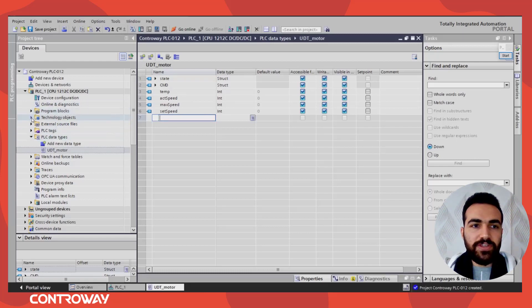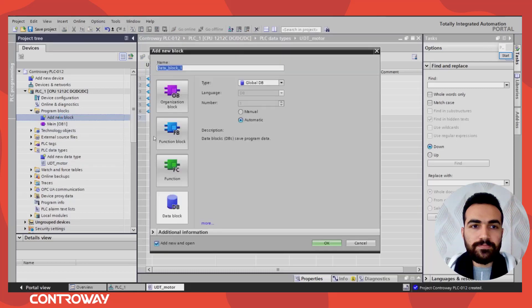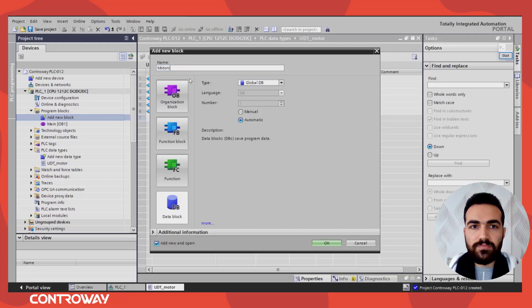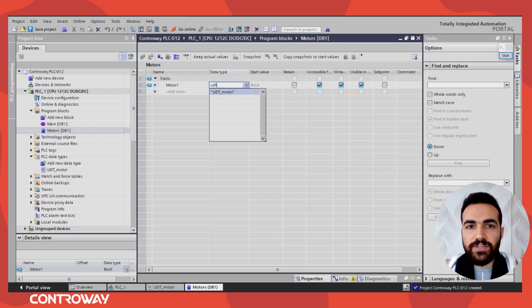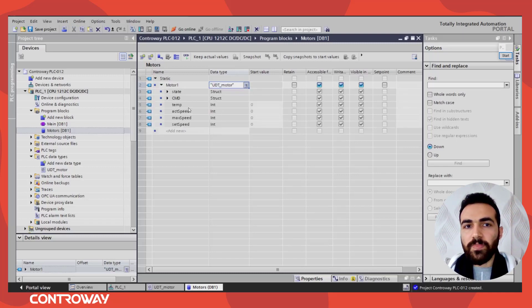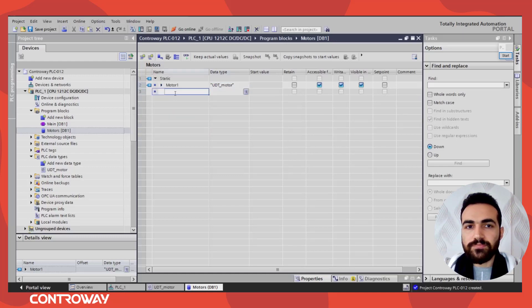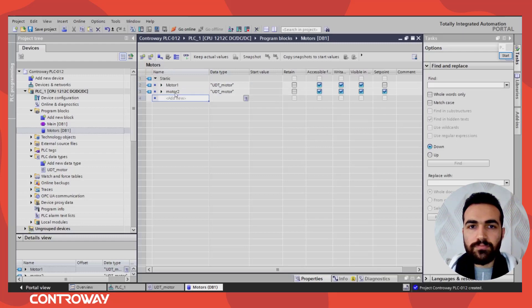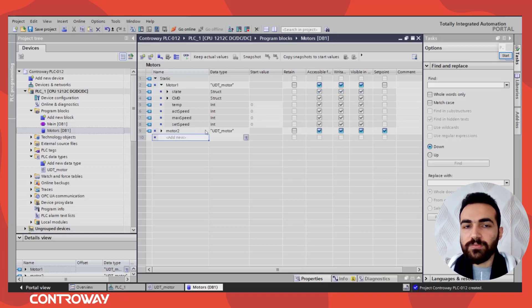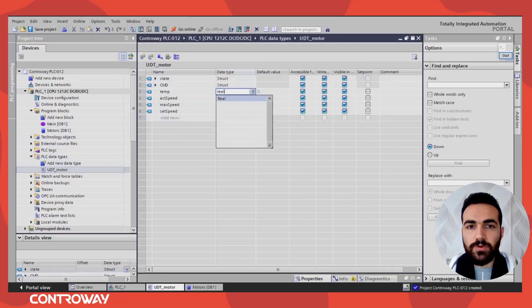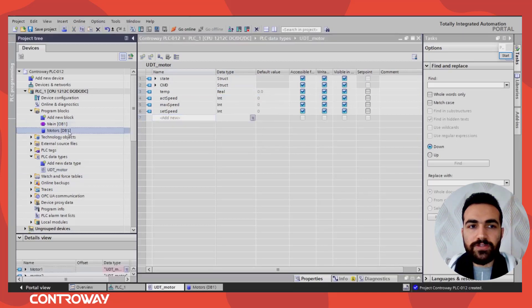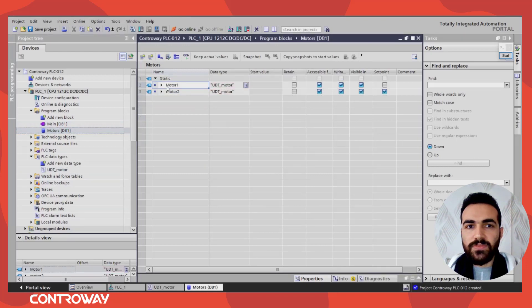Now that we have the data type, let's add a data block. Inside this data block called 'Motors', I can define a new variable like 'Motor1' with the type set to our UDT Motor. Now I have all those variables inside Motor1. For Motor2 there is no need to write it all again. If I need to update anything — for example, change temperature from integer to real — I update it in the UDT and it will ask if you want to update the interface. Now it will be a real value.